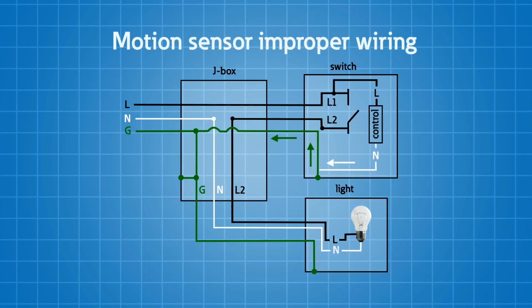But when you install a product like a motion sensor switch, which needs to have power, you need a neutral conductor to provide the potential voltage to power up the electronics. If I opened up a light switch and I don't have that neutral conductor there, I could get that power by taking hot to ground, the equipment grounding conductor, to power up that unit, and it will work. But it would put current over the equipment grounding conductor.